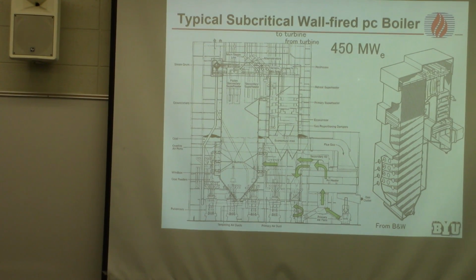But which way is the flow flowing? This way. So which way is the flow supposed to flow? The other way—and they actually do this deliberately. So the air comes out like this and creates what they call an internal recirculation zone. It sucks, the air splits out and then comes back and recirculates here, slowing down those coal particles so they stay in this region where gases are just circulating like this.